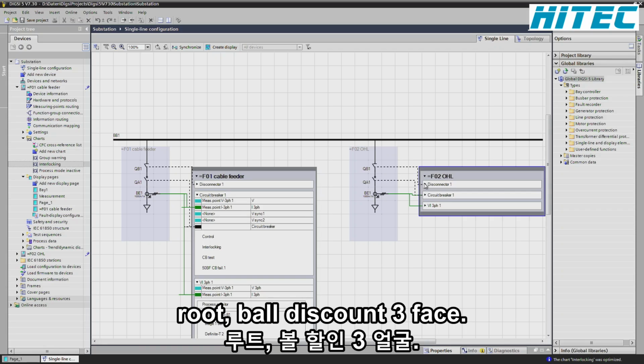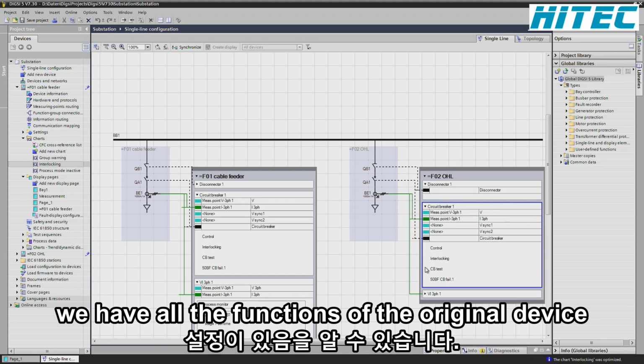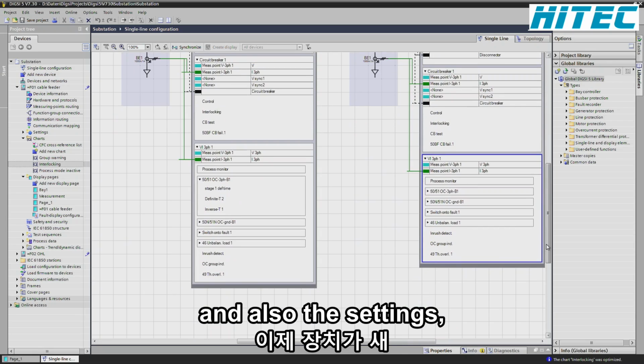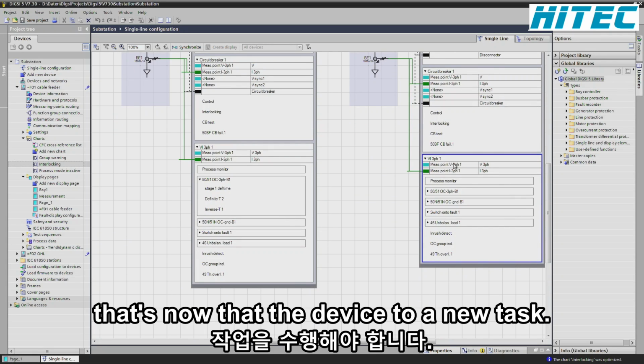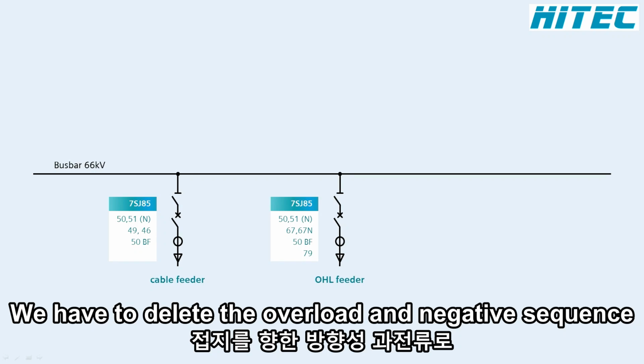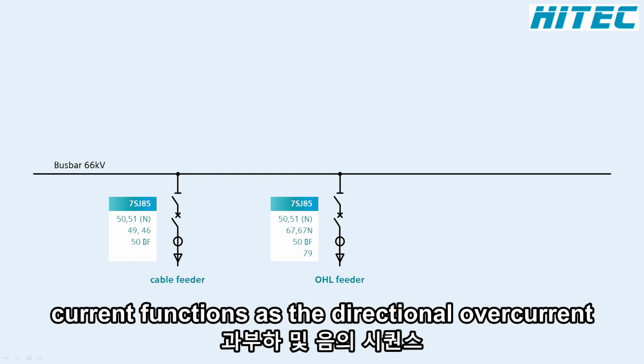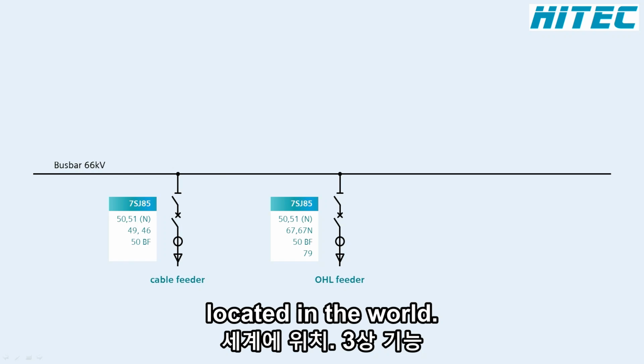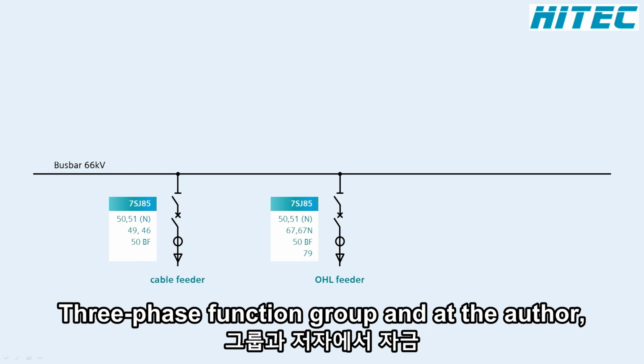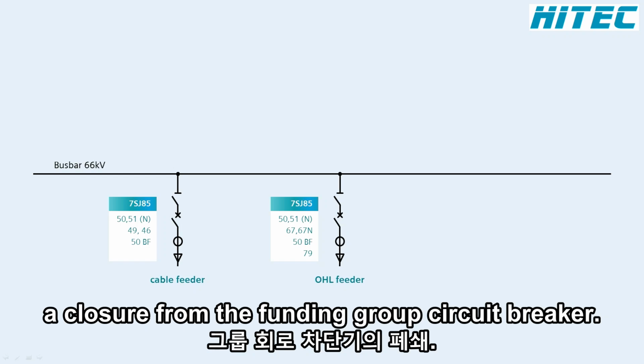Opening the function group voltage current 3-phase, we see that we have all the functions of the original device and also the settings. Let's now adapt the device to the new task. We have to delete the overload and negative sequence current functions, add the directional overcurrent phase and ground located in the voltage current 3-phase function group, and add the auto reclosure from the function group circuit breaker.